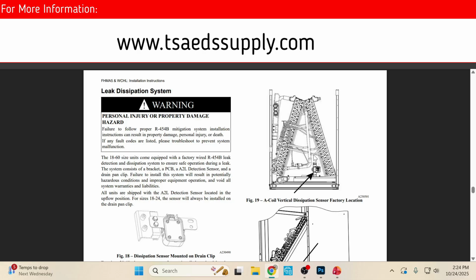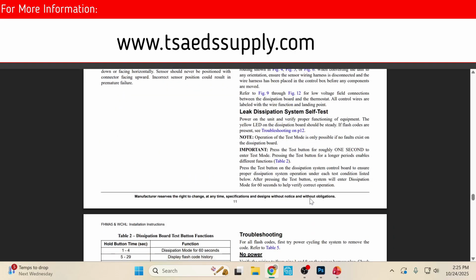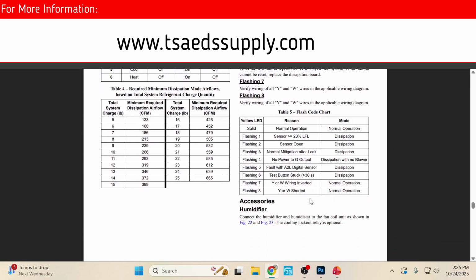the drawing here, usually if you have a leak on the ICP evaporator coils because your airflow is off, it's going to pop that feeder tube right there. And I thought it was interesting how they put their sensor right here, right underneath where that most common leak and crack when your airflow is off is right here, and that goes right into the sensor. So that's just something I want to kind of point out there. Here's your code for your dissipation board. If it's solid, it's normal. When you cut it on, you'll hear that blower motor run about 15, 20, 30 seconds, and it'll stop.